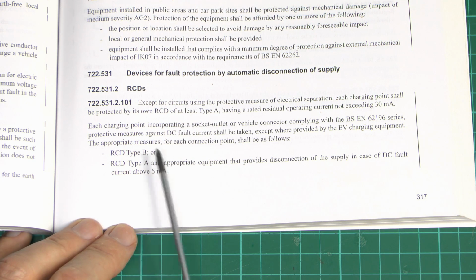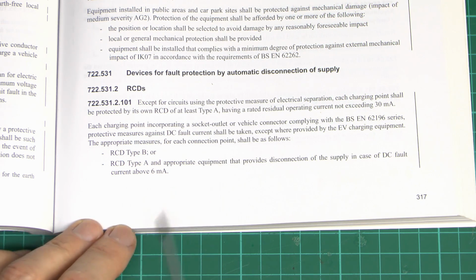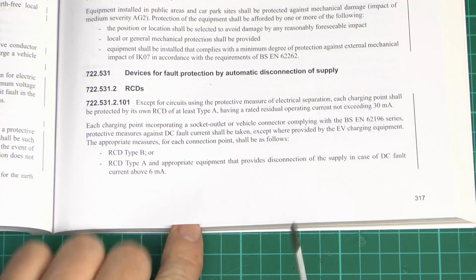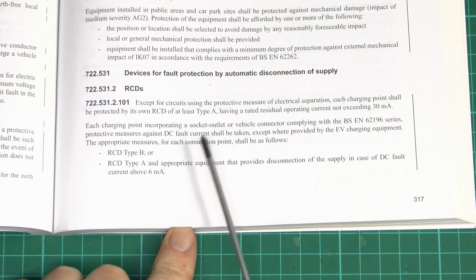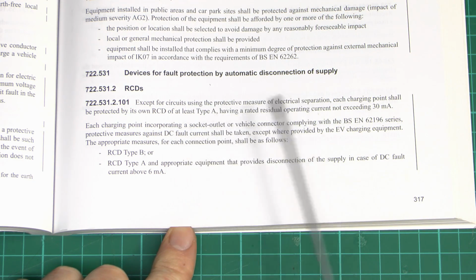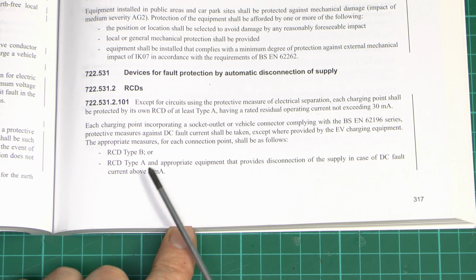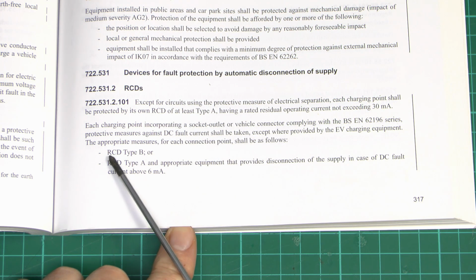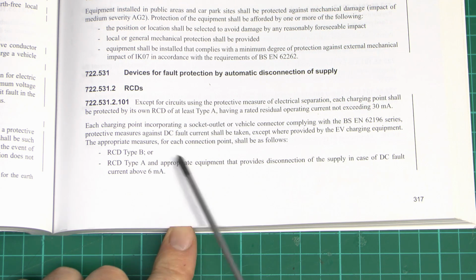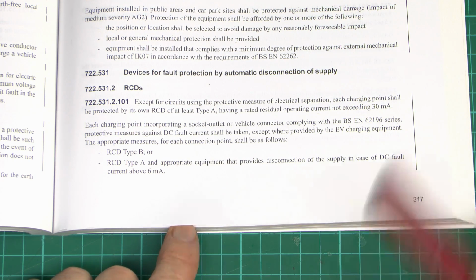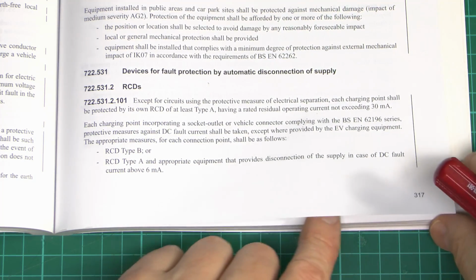Now of course you can buy RCDs of these particular types, and in fact one specifically designed for electric vehicle charging points. However, in reality the RCD is generally going to be incorporated into the charging device, so the circuit from your supply, it's going to say things like armoured cable or whatever, it doesn't actually need an RCD, and this is going to be built into the charging equipment. In the unusual case where the charging equipment does not have an RCD in it, then you would of course need to provide one, generally inside the property for that particular circuit, but in most cases it's going to be part of the charging equipment, so again not something you need to desperately do as a separate item.